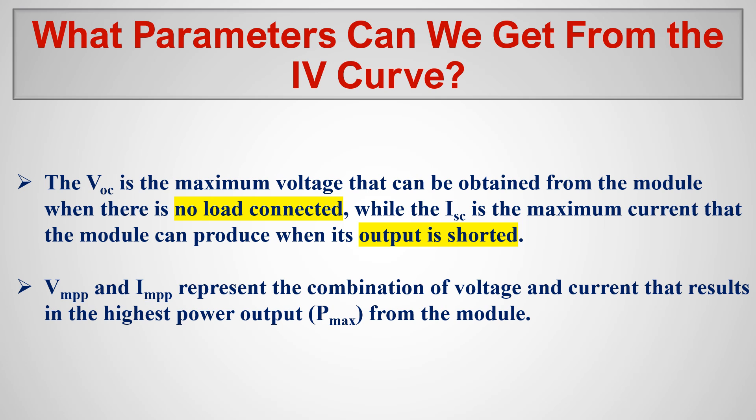The open circuit voltage is the maximum voltage that can be obtained from the module when no load is connected. The short circuit current is the maximum current the module can produce when the output is shorted. These two are specified on the panel because they tell us what safety measures we must take when designing the system — both the open circuit voltage and short circuit current are dangerous.